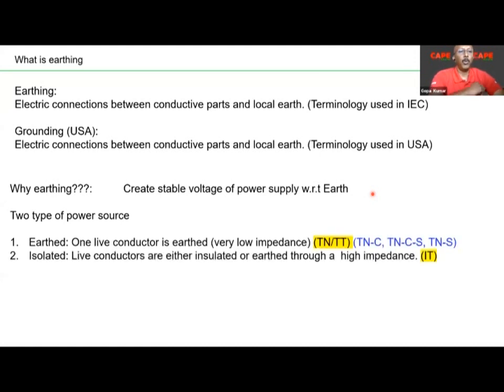Now, there are two types of power sources. One is called an earthed system. In an earthed system, one live conductor is earthed through a very low impedance. That means a direct connection: you take a wire and connect one of the lines to earth. Here the word earth doesn't mean an earth electrode in soil. It means a bus bar. That is called an earthed system, which is generally termed a TN or a TT system. TN is subdivided into TNC, TNCS, and TNS systems.